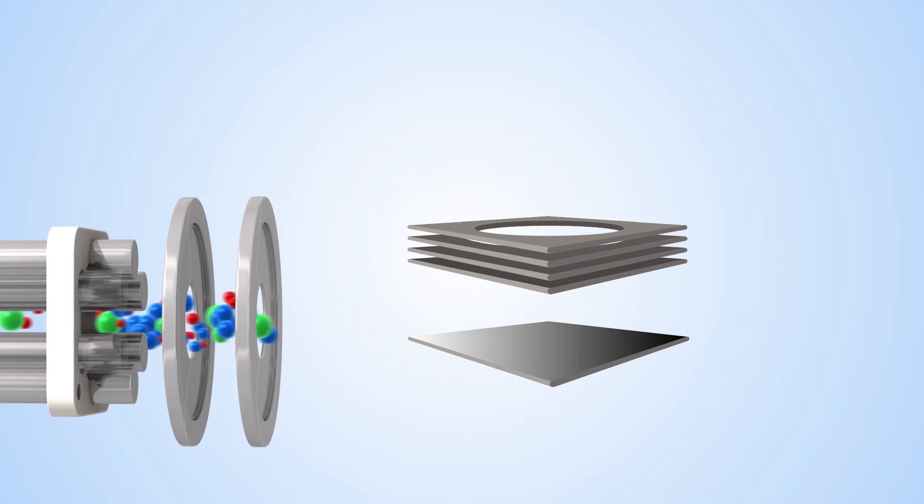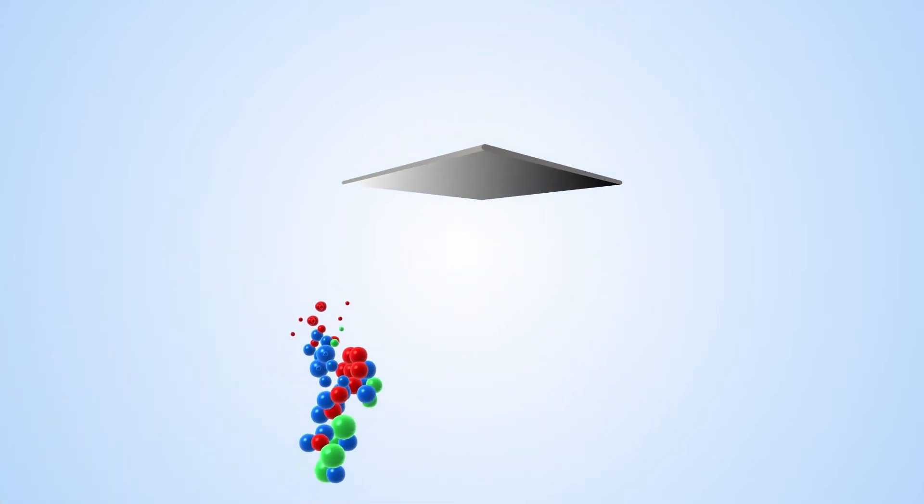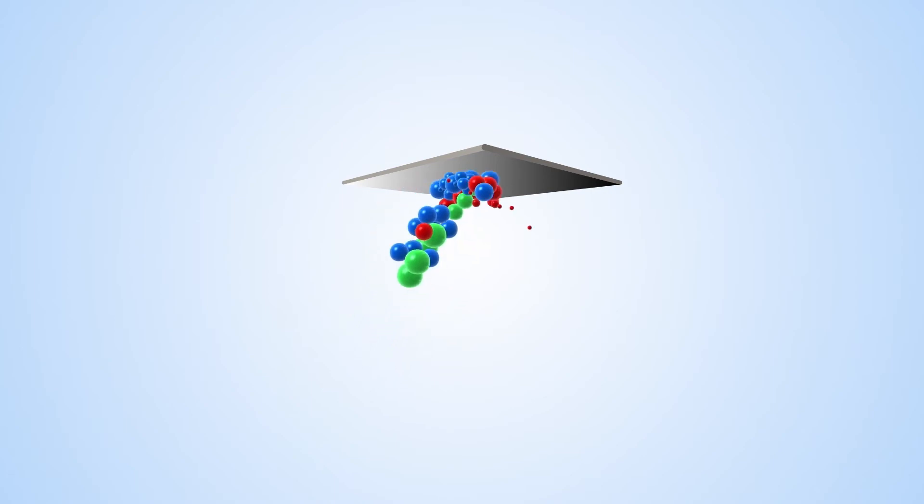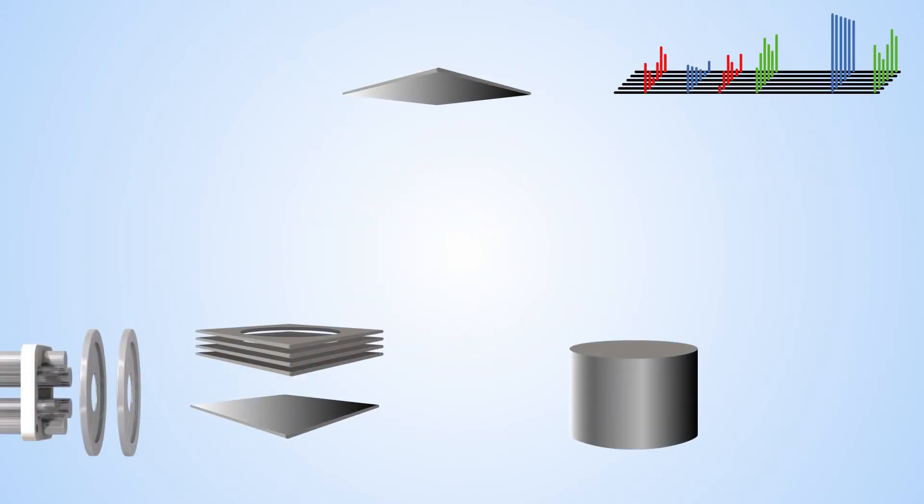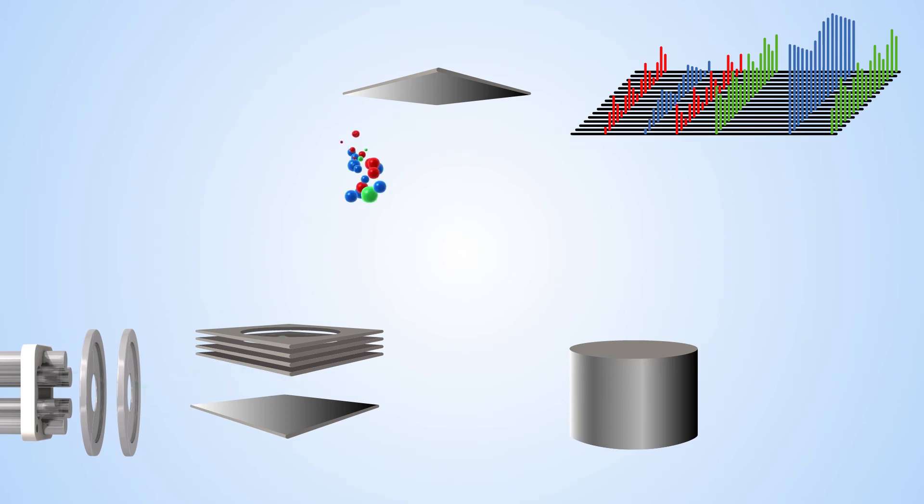Voltages manipulate the positions of analyte ions with frequencies related to their mass-to-charge ratios. When fragmented, all ion peak abundances are modulated at the frequency of their precursor ion's mass-to-charge ratio. Each fragment ion is then related to its representative precursor analyte ion.